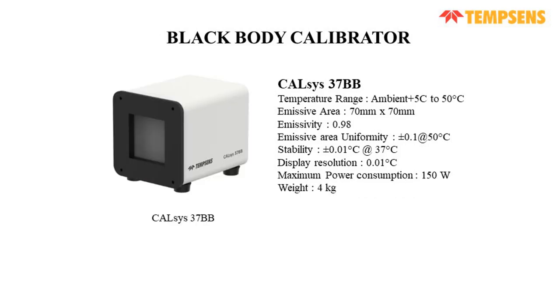The 37 BB plus comes with a reference RTD. You can insert the master RTD from outside also, and this is the 37 BB. It has the same specification as the 37 BB plus. With ambient, the temperature range will be ambient plus 5 degrees centigrade to 50 degrees centigrade, with an emissive area of 70 by 70 mm and emissivity of 0.98. The emissive area uniformity will be plus minus 0.1 at 50 degrees centigrade, stability is plus minus 0.01 degrees centigrade, and display resolution is again 0.01. Maximum power consumption is 150 watts, and weight is just 4 kg for this calibrator.